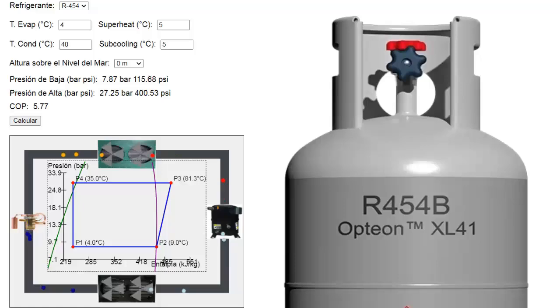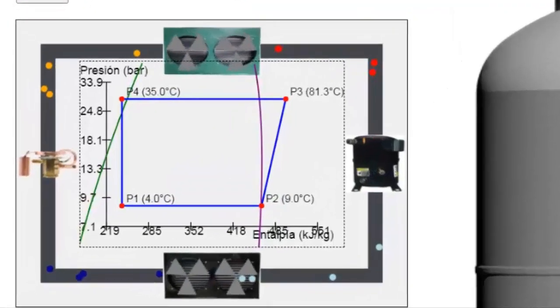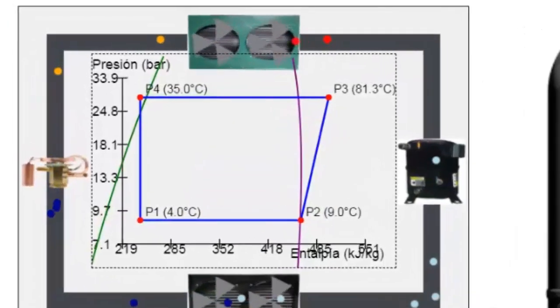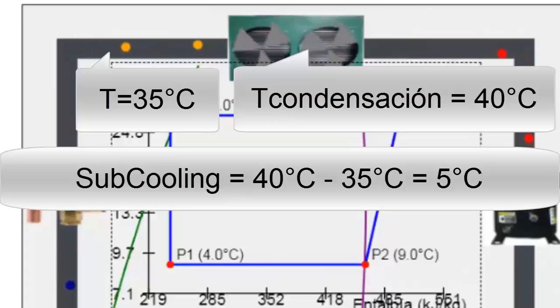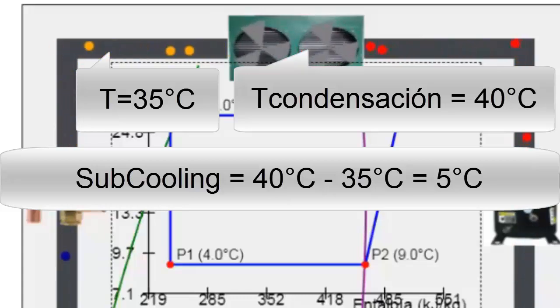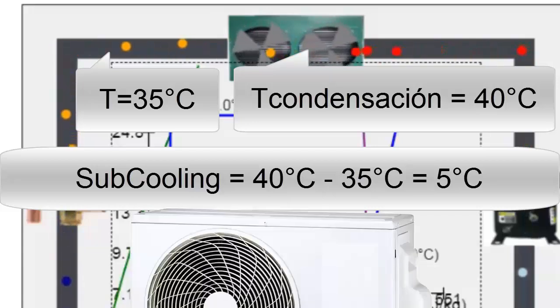For instance, if the condenser's outer surface is clean and there is adequate airflow, slightly higher subcooling values can be achieved. However, it's important to note that in hot climates or under unfavorable heat exchange conditions, such as low fan speed or a dirty condenser coil, subcooling can drop below 5 degrees Celsius and even reach 0 degrees Celsius.